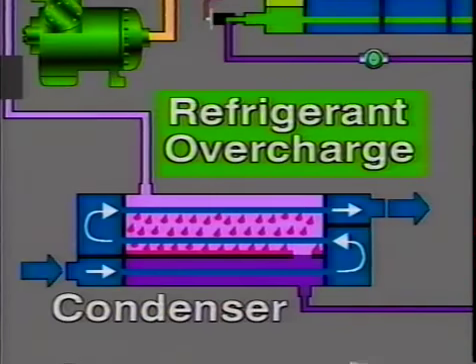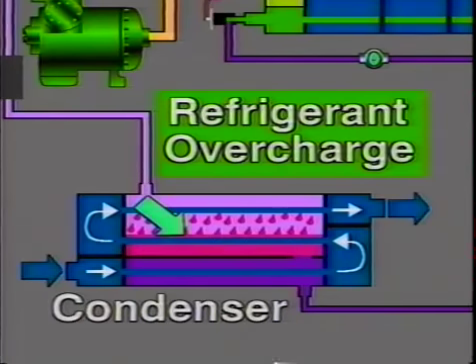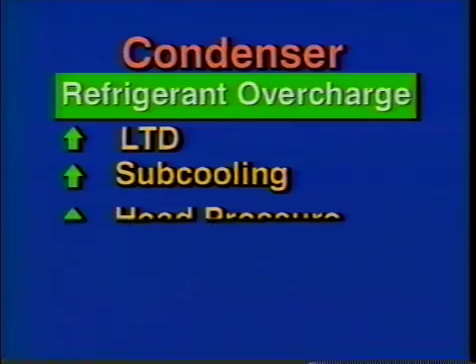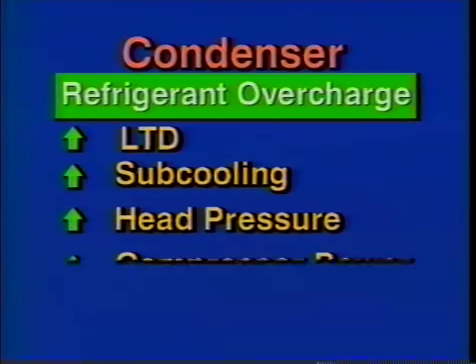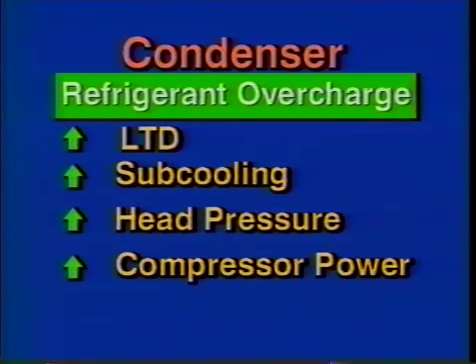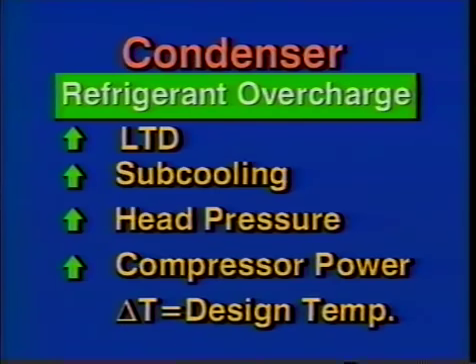A refrigerant overcharge causes more liquid to back up in the condenser and fewer tubes are available for the condensing process. With this situation, we would find the LTD and subcooling higher than design, head pressure elevated, and compressor power high with capacity somewhat reduced. We would also typically see the full 10-degree delta T across the condenser water.